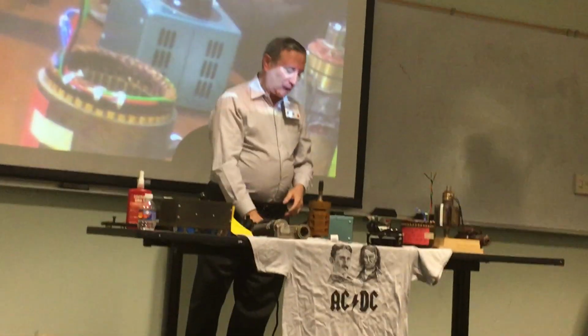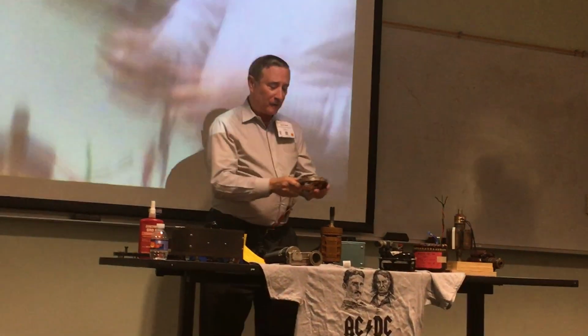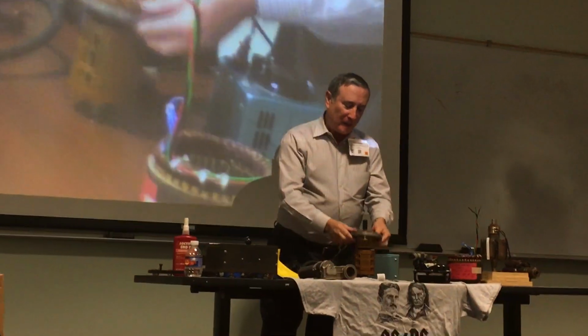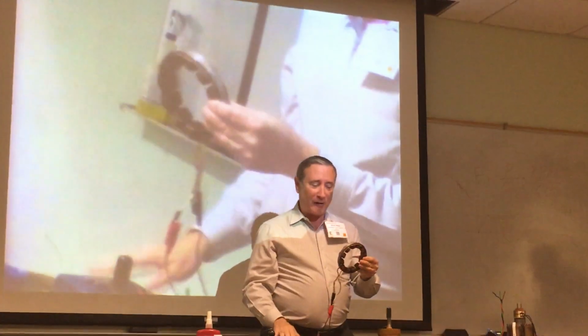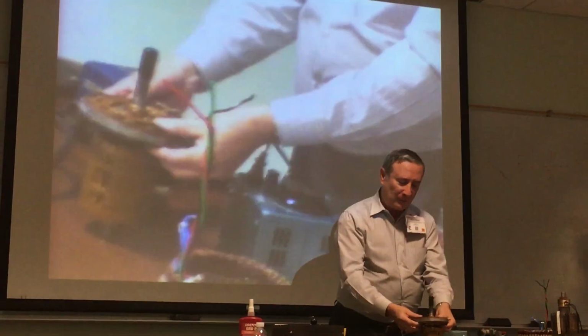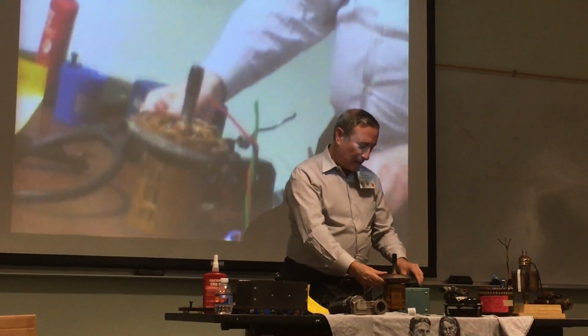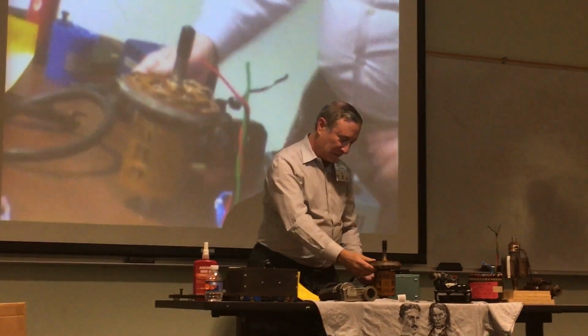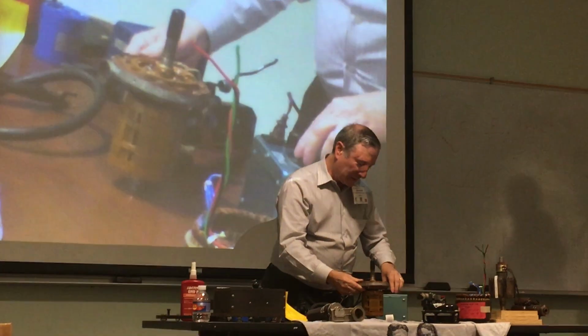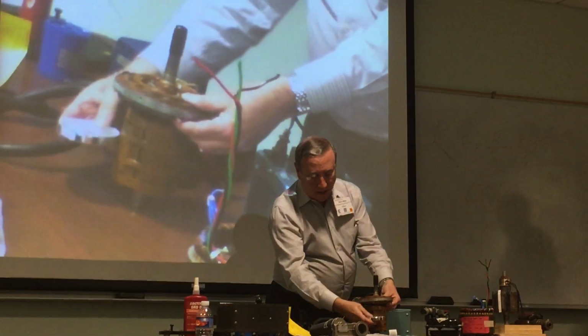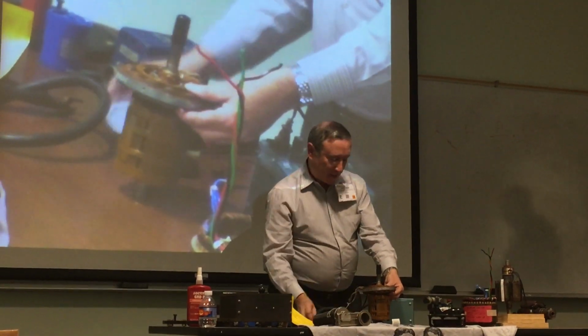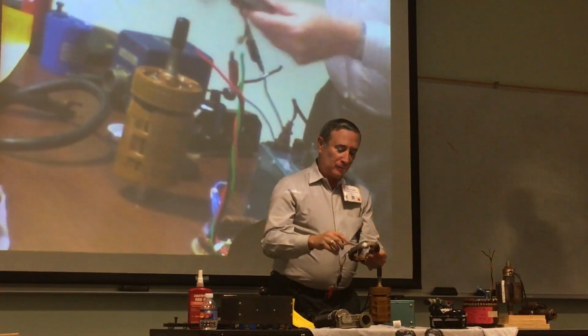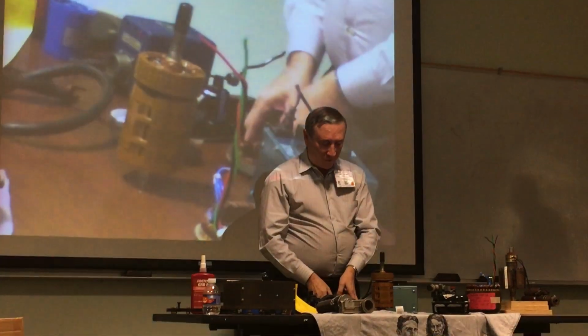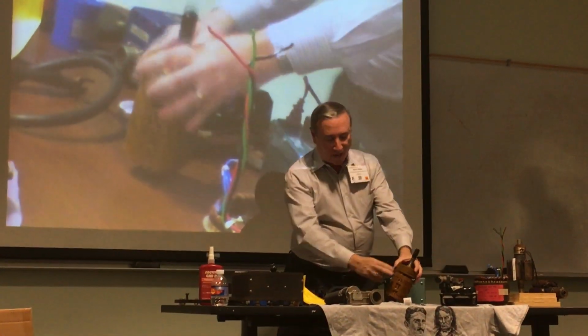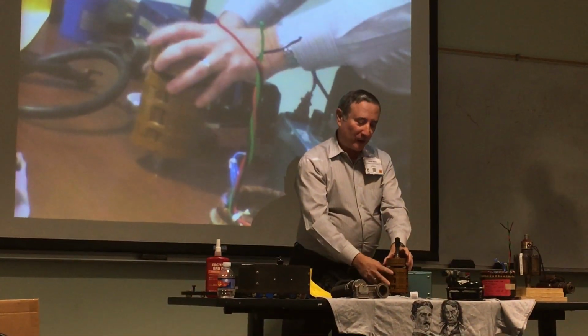One of the really cute tricks we have of testing the rotor, since we can't turn it on a workbench, is that instead of putting DC into this from the regulator, we can put a small amount of AC into it and fool it to think it's turning. So I can put some AC into the top. Is that a variac? Yeah, it's a variac. And now we get north-south, north-south again on the compass. And with this simple little trick, we're checking that the exciter stator is good, the exciter rotor is good, the diodes are good, and the main windings are good, all with that little trick. Saves our technicians a lot of time.